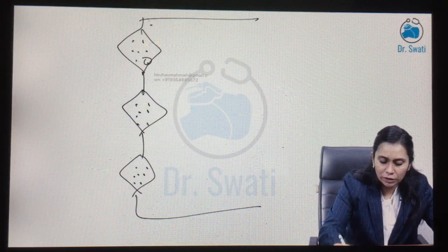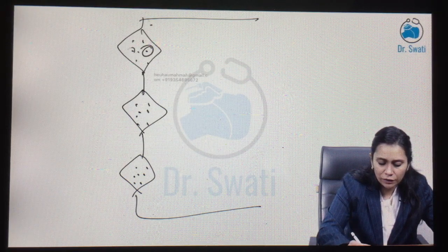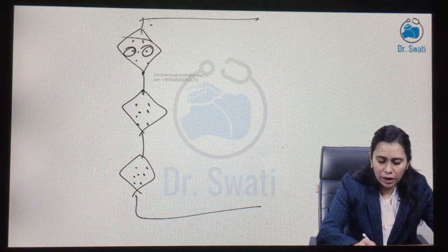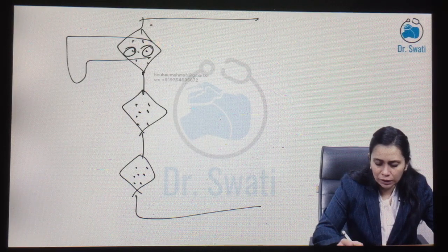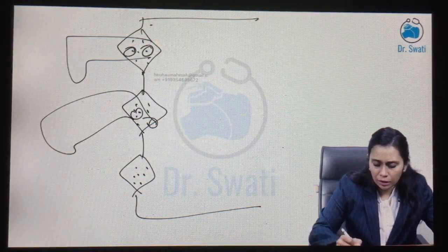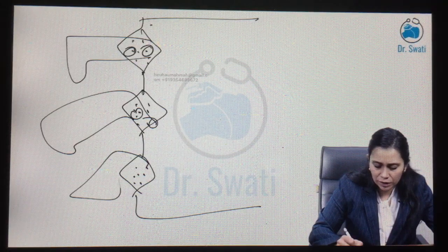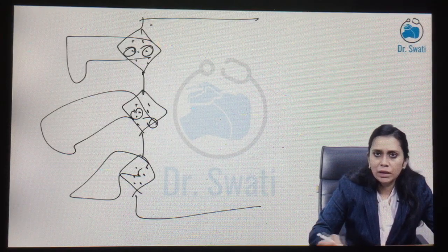This is the oxygen attachment site, so the second and fifth pins are active. We attach oxygen. For nitrous oxide, the third and fifth pins are active. We attach nitrous oxide. For air, the first and fifth pins are active. We attach the air cylinder. So the cylinder is attached.